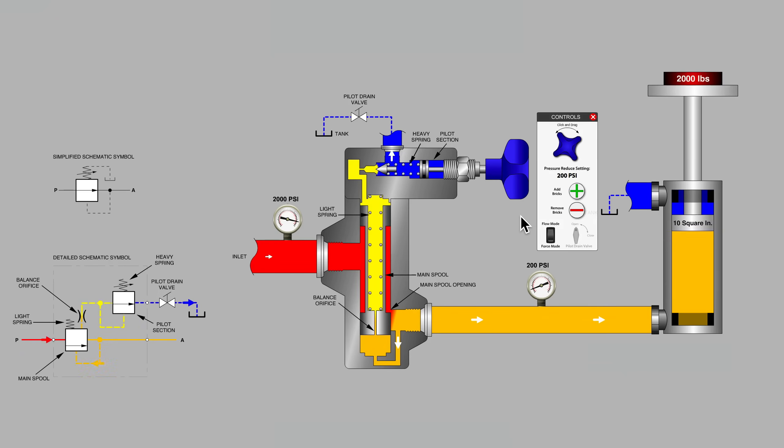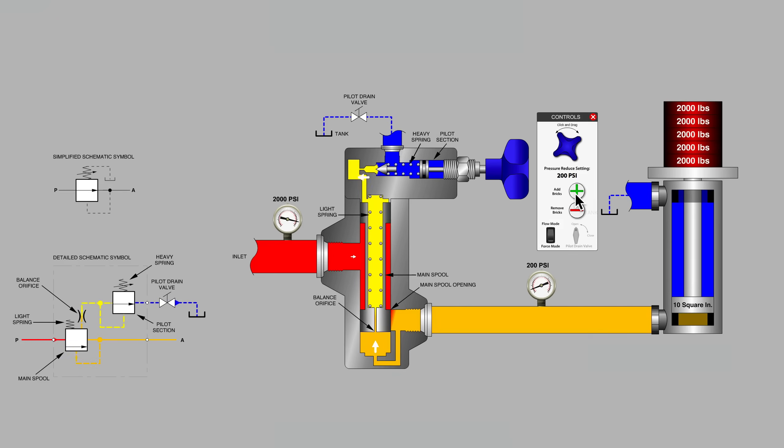A pressure-reducing valve is used to step down a higher system pressure to a lower maximum value in a downstream sub-circuit. The internals of the valve don't really become active until there is considerable resistance on the outlet.